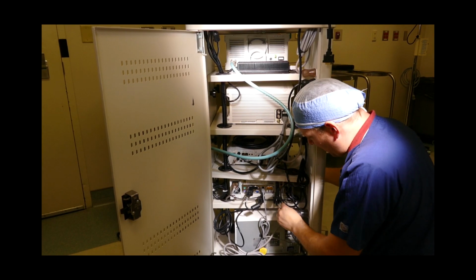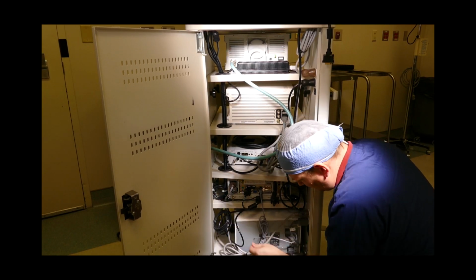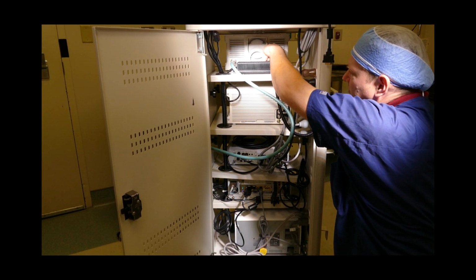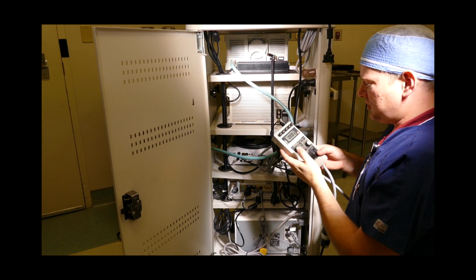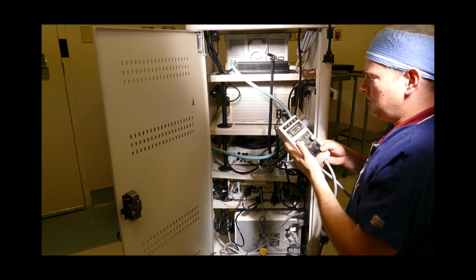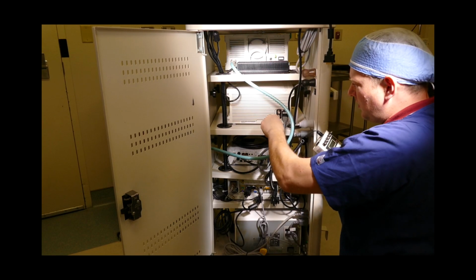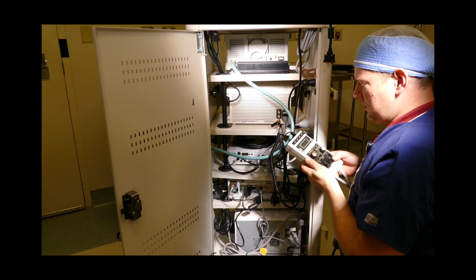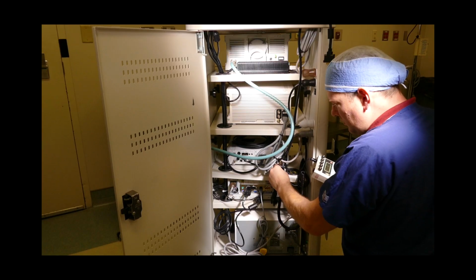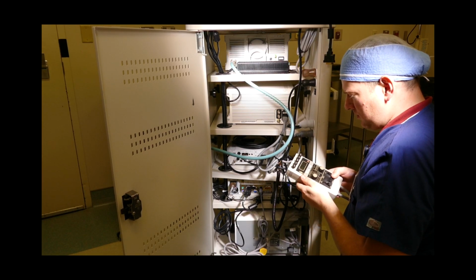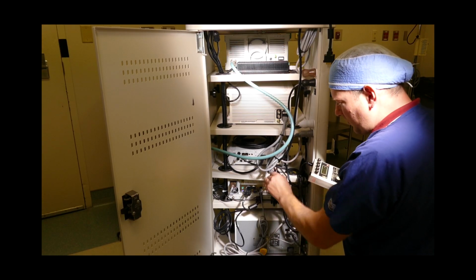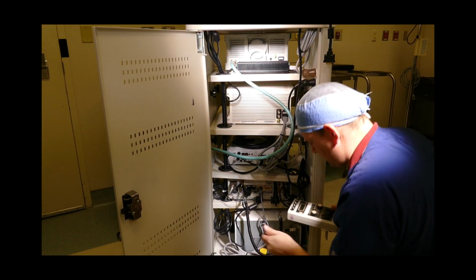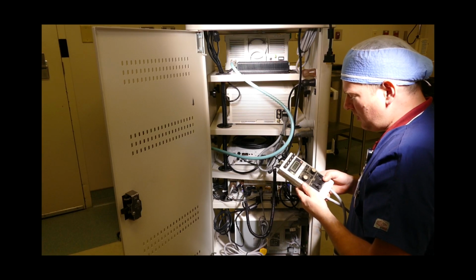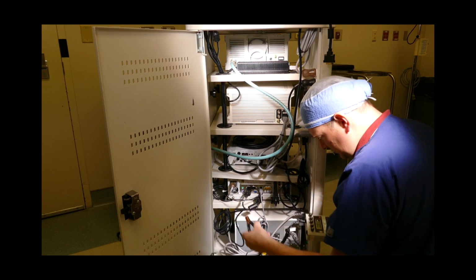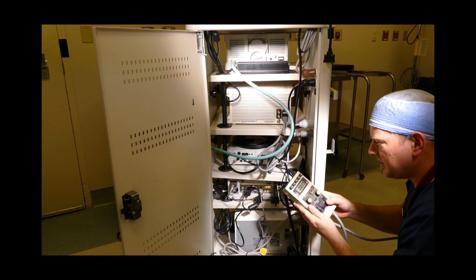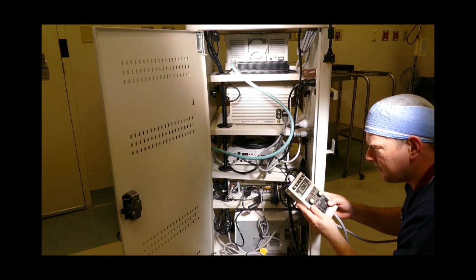I'm going to check the cords to make sure they're all firmly inserted. I'm going to start at the top device. Enclosure leakage, lift ground, 7 microamps, 7 microamps, 6 microamps to 7 microamps, got 2 microamps, and 7 microamps. In the bottom unit, we have 1 and 7 microamps.